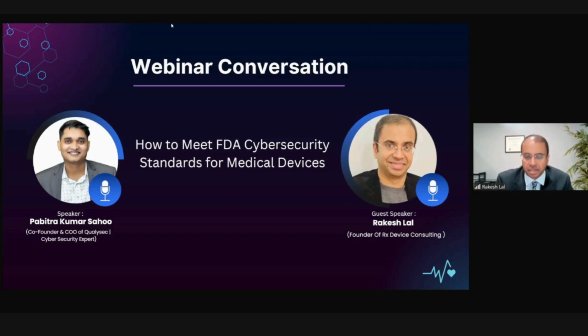In a 510(k) application, FDA reviews the submission and compares the characteristics of your device against a legally marketed predicate device. This is another device that has previously been cleared by the FDA, and you are basically claiming in your submission that your device is very similar to the predicate device. There are no unknown risks or unknown hazards that this device can pose to the patient. So it's very similar to that one, so use that as a guide to process this submission is what you would essentially be telling FDA. And FDA will grant the clearance if they determine that your device is substantially equivalent to the predicate device.